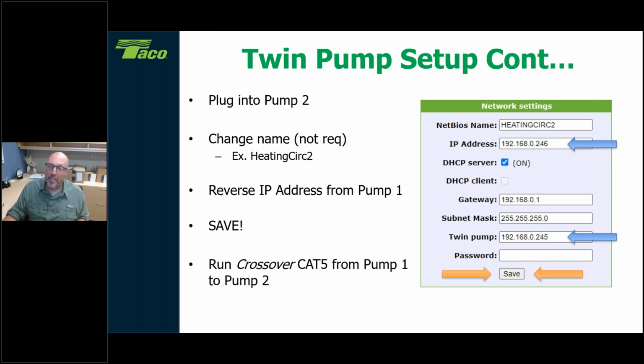And this, as Chet was asking before, is the point when you want to use a crossover cable. So once you're done, you disconnect your cable out of there, and you're going to run a crossover cable from pump one to pump two. Crossover cable just means the four wires in the middle of your Cat 5 cable are reversed. So yes, you're going to have the electrician or the IT guy on site to be able to make those cables anyhow. Just make sure it's a crossover cable, because otherwise it doesn't communicate properly. It will never see the second circ. So very important on that side of things.